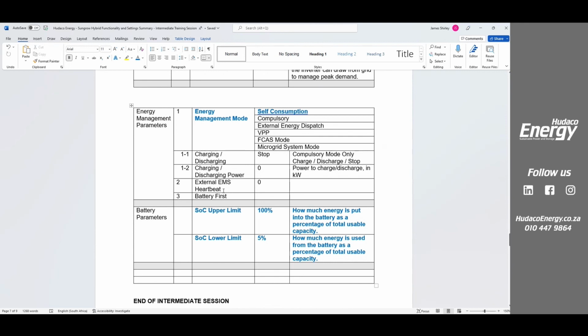And then we've got external EMS heartbeat. This is like Ripple Relay. I think that's actually designed for the Australian market, where we can receive a heartbeat from an external energy management system that says, okay, things are still okay. And as long as things are okay, we keep doing our same thing. If that heartbeat changes, it'll change its mode of operation. And then battery first. Here we can say we want to charge the battery first as opposed to running loads first from PV. So you can set your priority there.